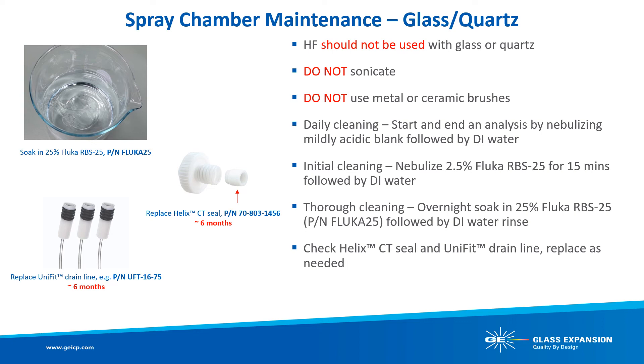Regarding spray chamber maintenance: with a glass or quartz spray chamber, hydrofluoric acid should never be used. Do not sonicate the glass or quartz spray chamber, and do not use a metal or ceramic brush to clean the surface, as all of these techniques will likely damage or break your spray chamber. Always start and end analysis by nebulizing a mildly acidic blank solution followed by DI water. If performance degrades — washout issues, poor RSDs, or droplets collecting on chamber walls — it's time to clean. Try nebulizing a dilute approximately 2.5% Fluka RBS 25 solution for 15 minutes followed by DI water. If that does not recover performance, remove all fittings and soak overnight in 25% Fluka RBS 25 solution, then thoroughly rinse with DI water.